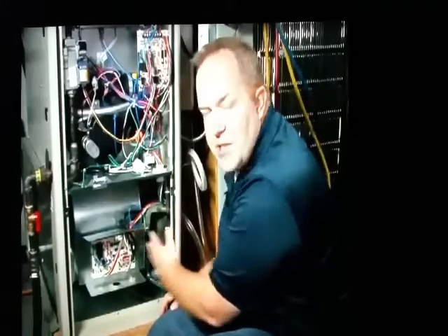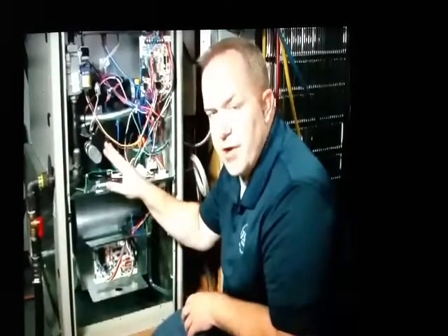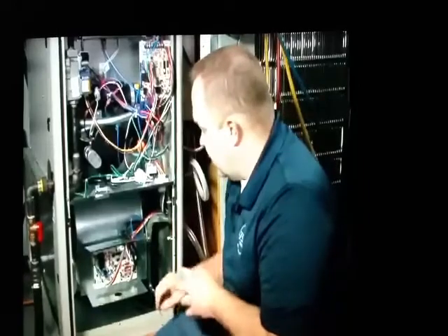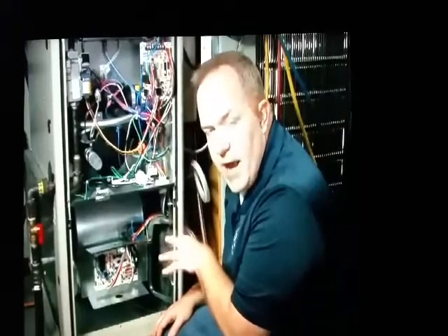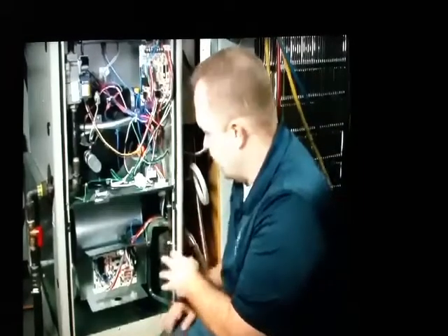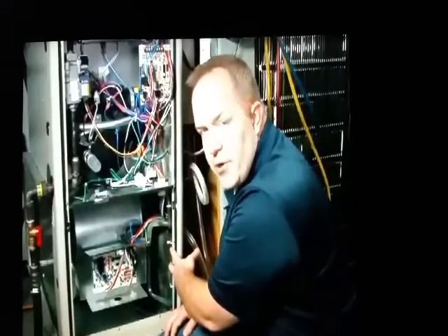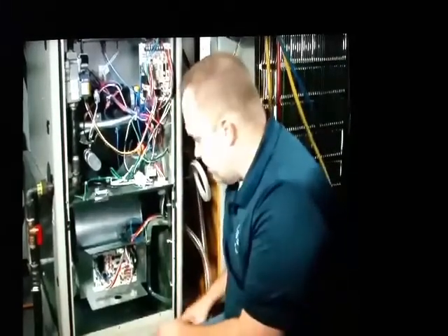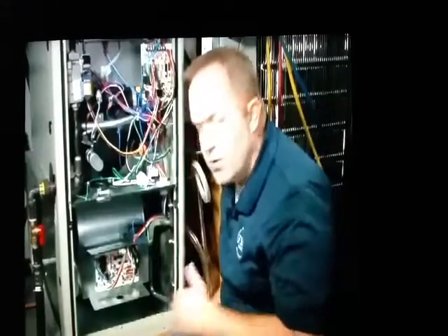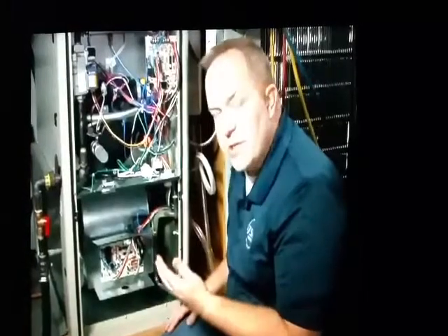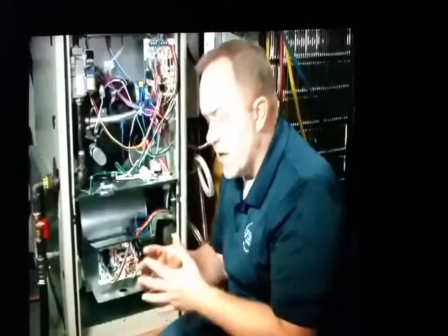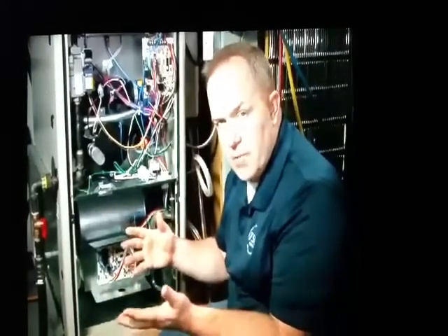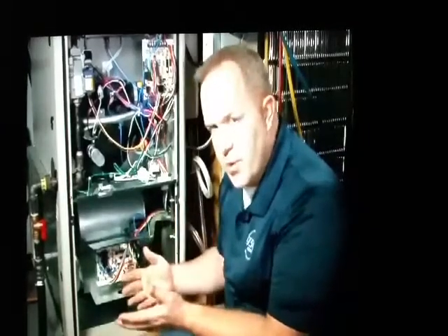The trap gives a vacuum break effect against the negative pressure of the inducer. The other important aspect that you want to pay attention to on your condensate plumbing of a high efficiency furnace is simply this. You already have a trap at the furnace. If you were to trap that drain line again, whether you did it purposely or not, if you were to introduce a second trap, or a double trap, if you will, what will happen is that those two traps then cancel each other out. It's almost as if you have no trap whatsoever.